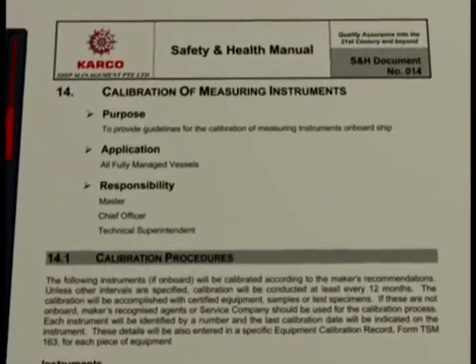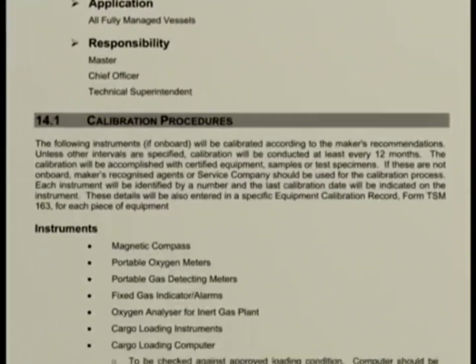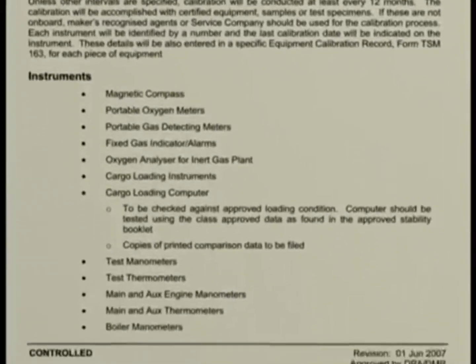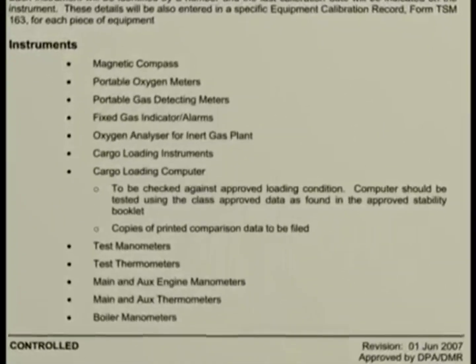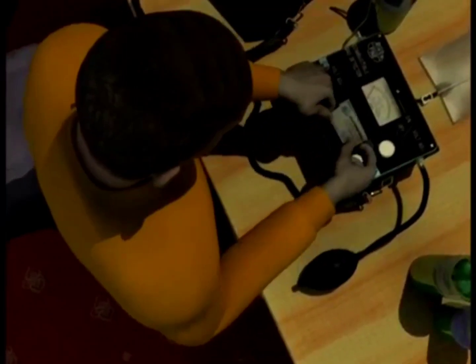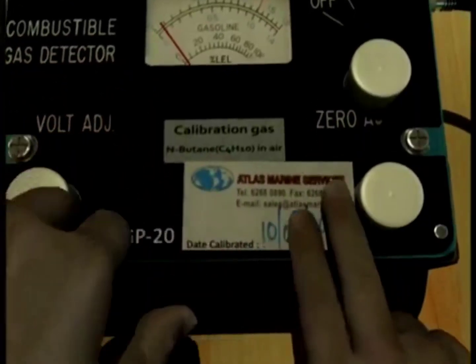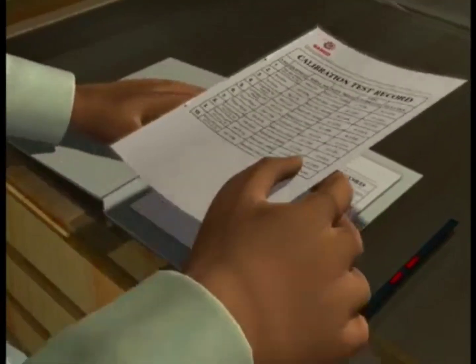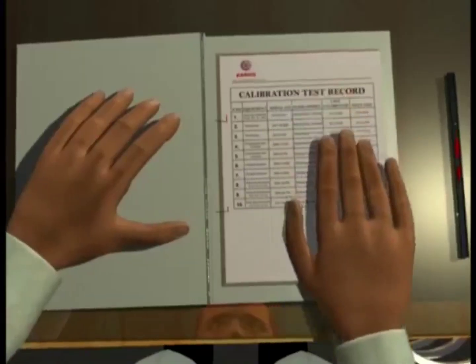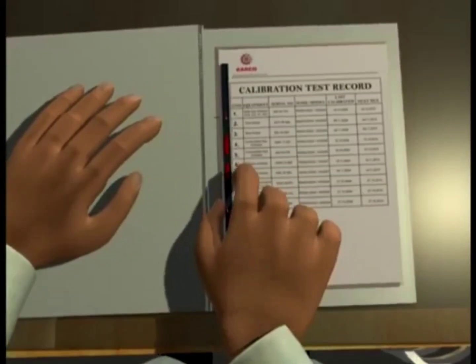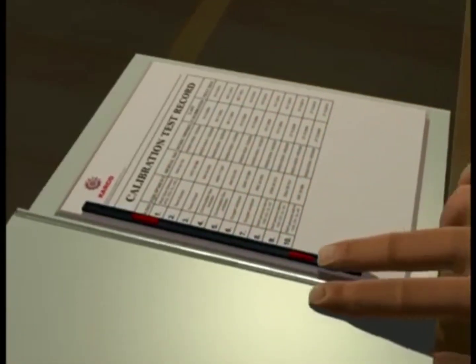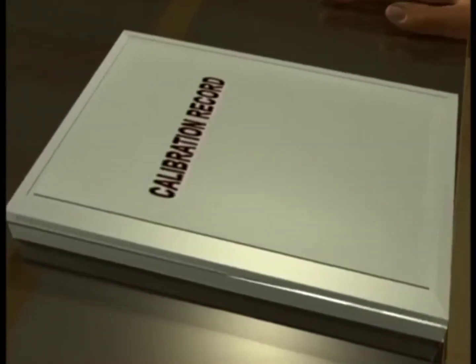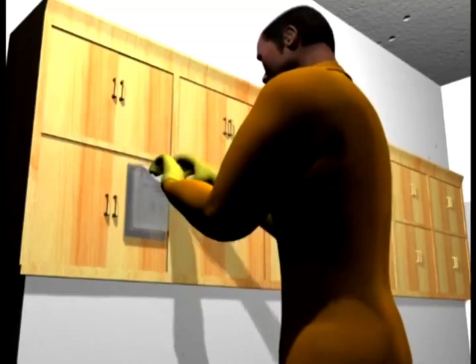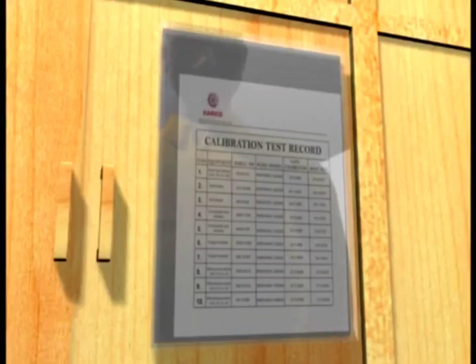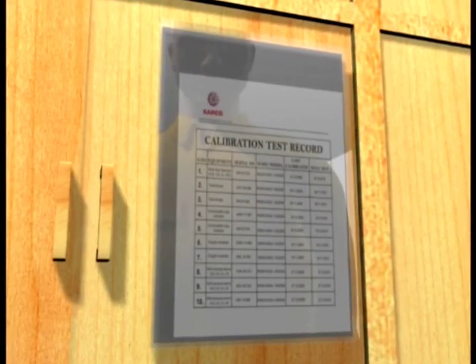The company regulations require all portable and personal meters to be calibrated by ship staff before every use and by a shore-based facility annually. All the meters are to be marked with their last shore-based calibration date and the certificate of same filed for reference as required. A printout of the inventory record of the meters, the span gas, the calibration dates of the meters, the expiry date of the span gas should be prominently displayed at the location where the units are stored.